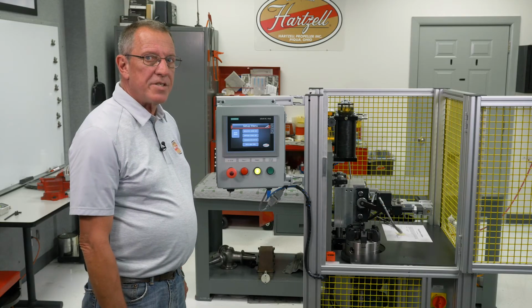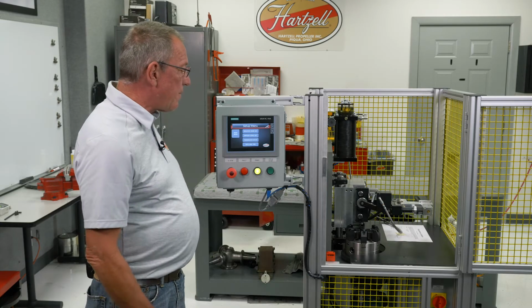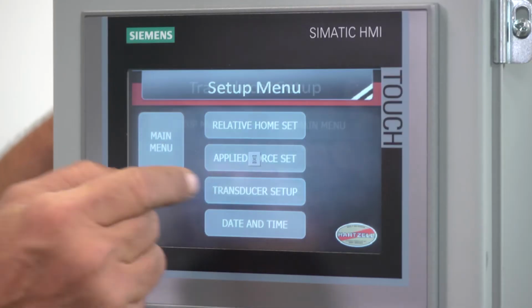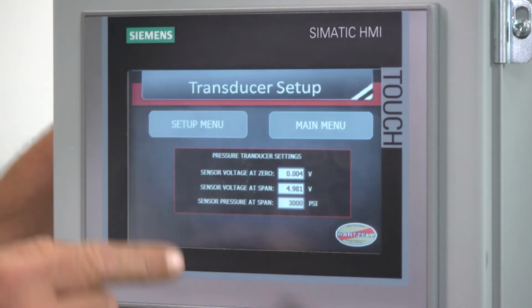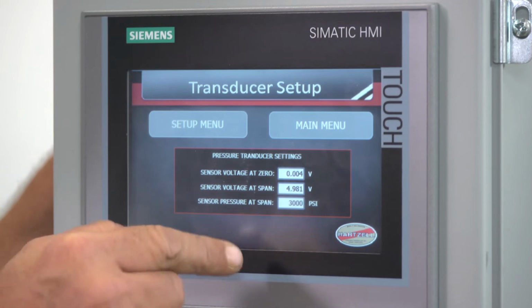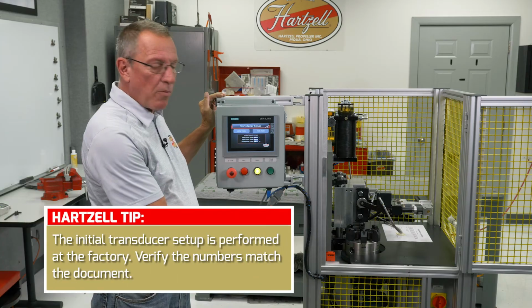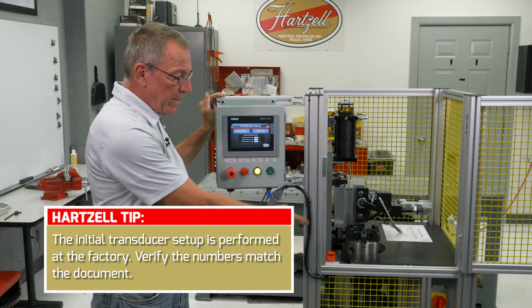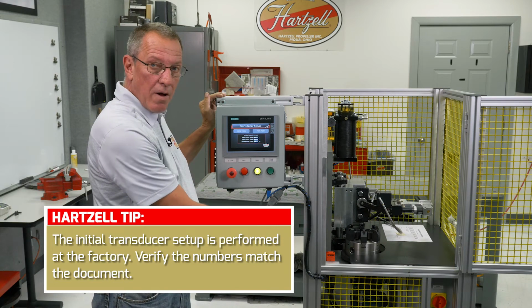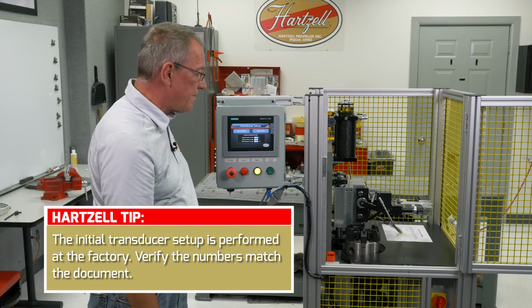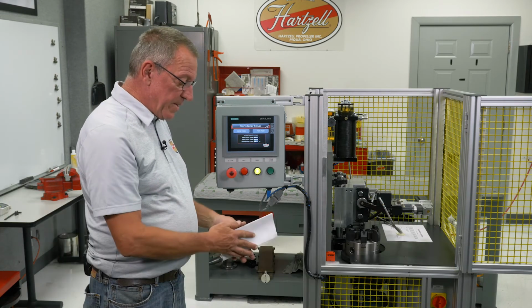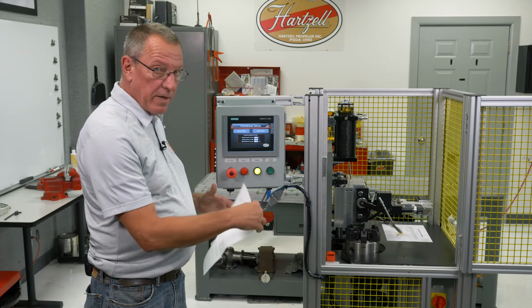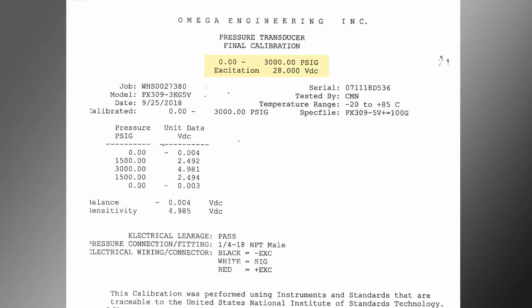The next calibration step is the transducer setup. So we'll hit the transducer setup button. And these settings here are based on the calibration paperwork which is included in the machine. It's inside the door of the fuse access. And you'll have a piece of paper that looks something like this. The pressure transducer is a 0 to 3,000 psi transducer.